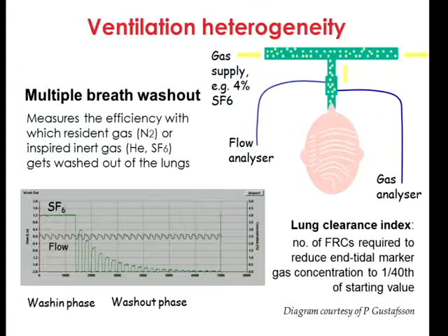A carbon dioxide sensor, for instance, works on infrared principles. Whereas for anything else, like nitrogen, if you're using nitrogen as your gas, or something like SF6, you would use chemiluminescence analyzers. Those are a different breed again. Or you can also use a mass spectrometer. That's another way to analyze gas components, which is very similar to what you use in chemistry.